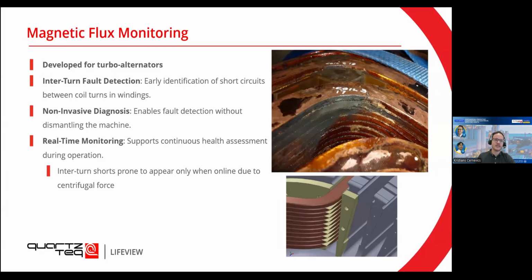This solution is developed and intended for turbo alternators, for two-pole machines. It allows us to detect inter-turn faults, so we can detect shorts between the turns in the windings. So for your coils, you have a winding like this. And depending on the age of the machine, the condition or maybe some contamination, you can actually have a short between the windings. This is, again, non-invasive diagnosis. It enables us to detect the fault without dismantling the machine, same as for the partial discharges. It also allows you real-time monitoring, so continuous health assessment during the operation.